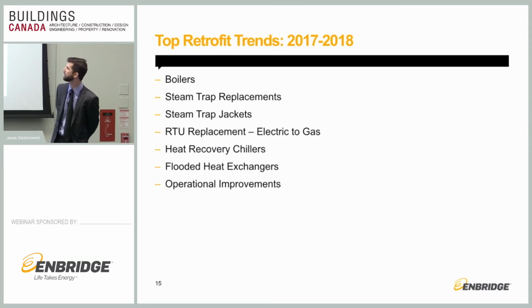Heat recovery chillers, it's kind of been under the radar, but I think a lot of deeper pocket customers are looking at that more closely in the next couple of years. Especially for buildings that have simultaneous heating and cooling in the winter. And you can't offset all of your heating load or your cooling load with free cooling, and you have to run the chiller in the winter. So we're finding now that there are technologies in the field that provide a lot of low-grade heat. You might get heat recovery from a chiller in the range of 90 to 120 degrees F, and that's good for certain capacities, but you can't really meet your heat load with that.